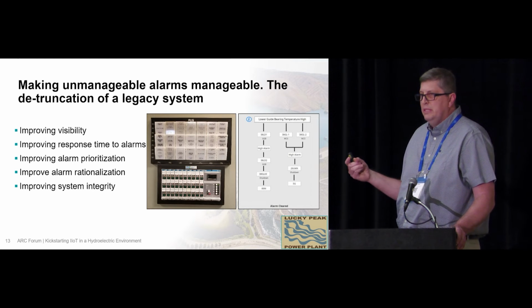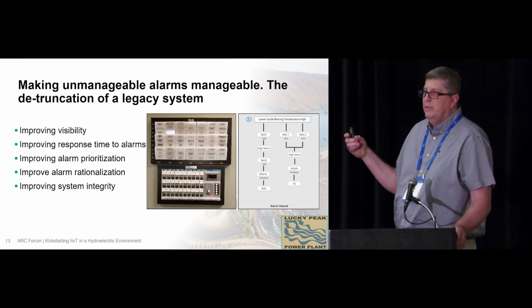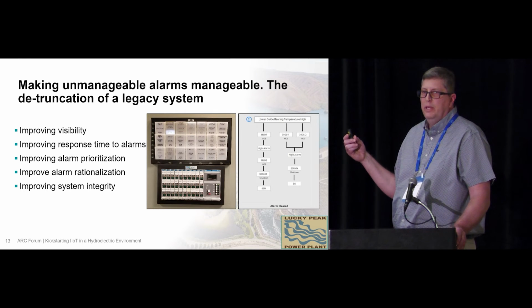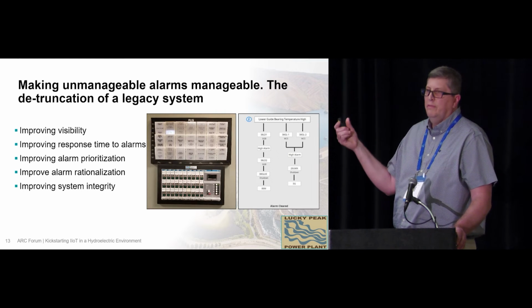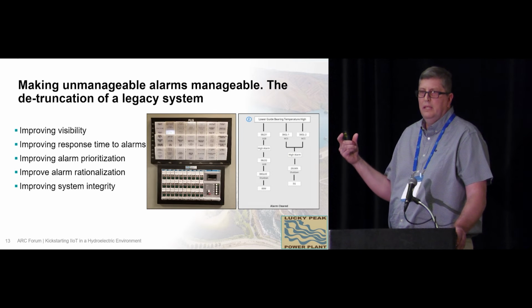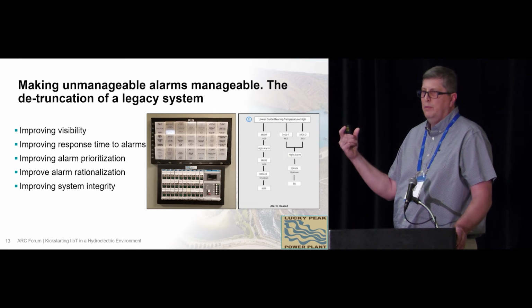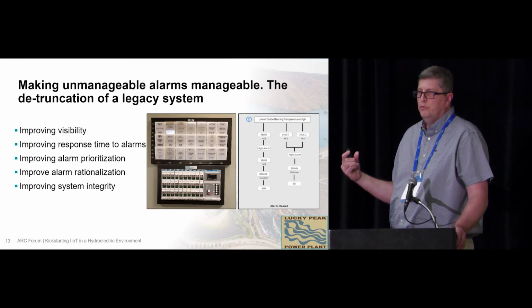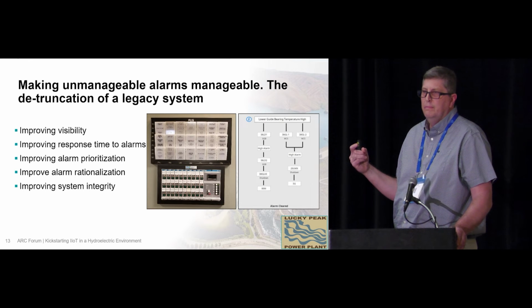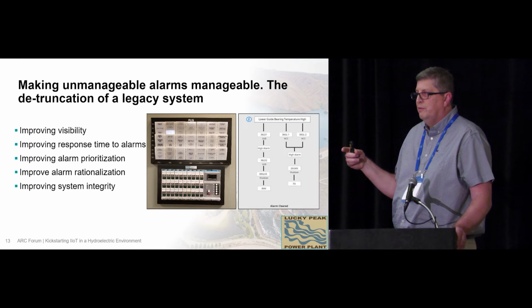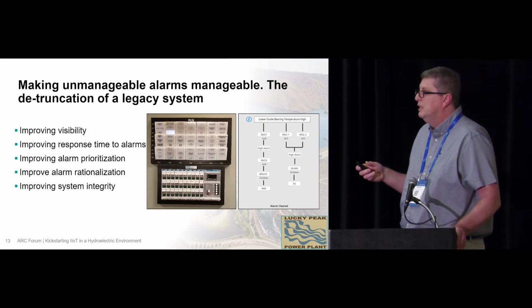There are a couple of reasons we wanted that. Sometimes there's logic involved with those end devices, so you can see not just that the device came in, but where in that logic the circuit is. Is it a timer? Are we five minutes from shutdown? Is it possible to stop that? Can we fix something quickly? Also, if something's supposed to go straight to shutdown and it's not lighting up or shutting down, you know you have a fault in your system. Having complete visibility over the entire circuit was important for us.